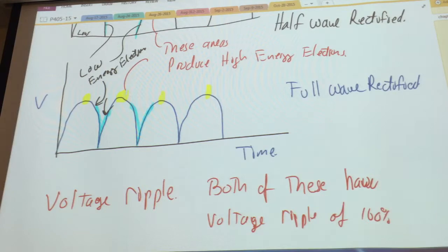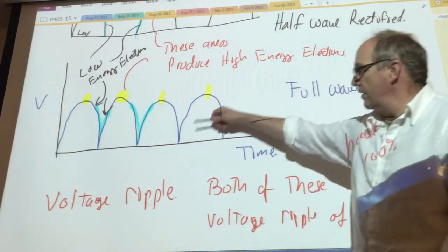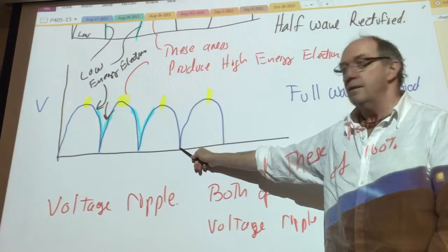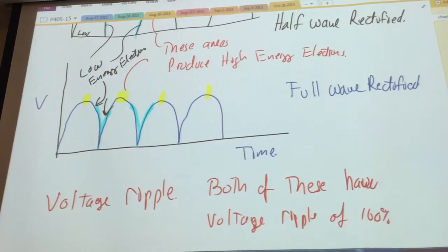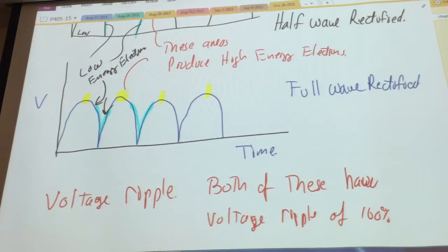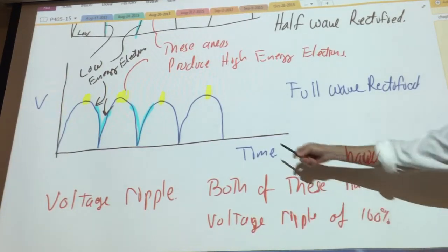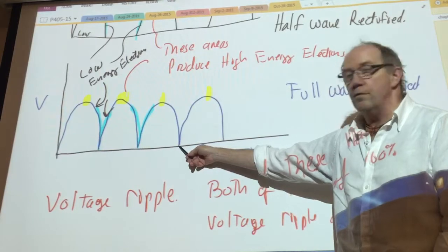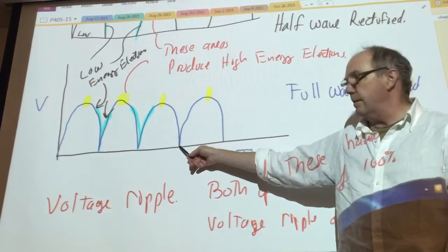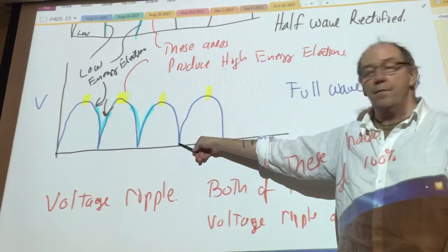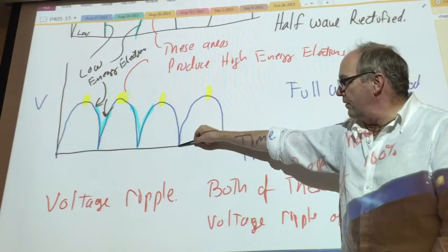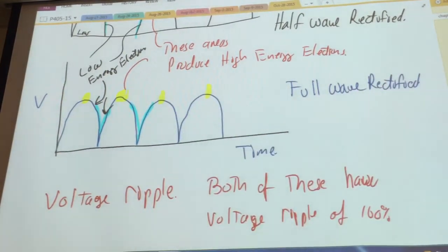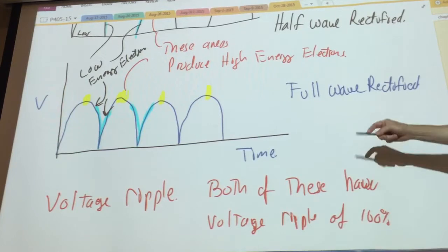But the voltage that's applied to the electrons goes from a low of 0 up to my maximum voltage. So that's just saying that the voltage going between the cathode and anode varies between 0 volts and 100 volts, 100%, the full voltage. When I'm applying 0 volts to the cathode, the electrons are not being accelerated. In this case, it's not for a very long time, but it does happen. And then at some point, the voltage increases from 0 all the way up to its maximum value. Hence, 100% voltage ripple.